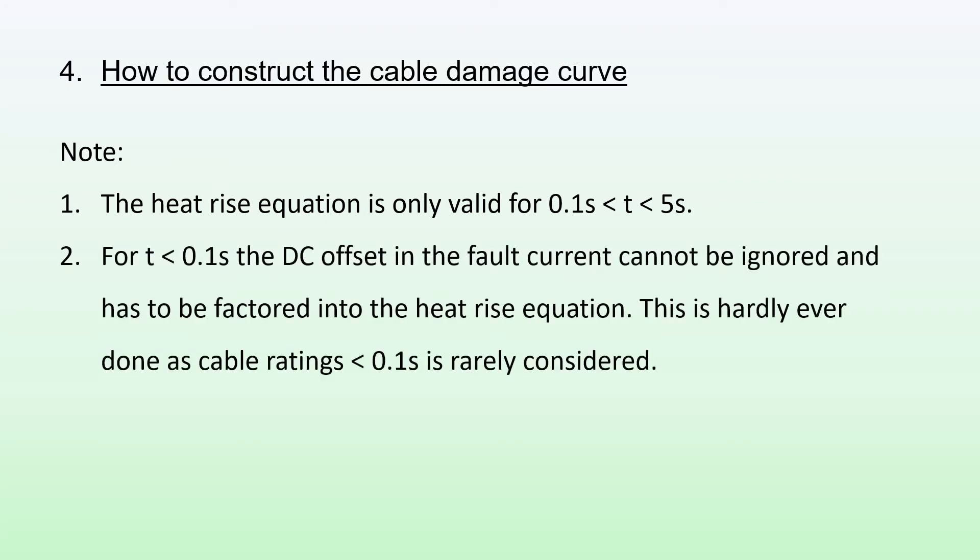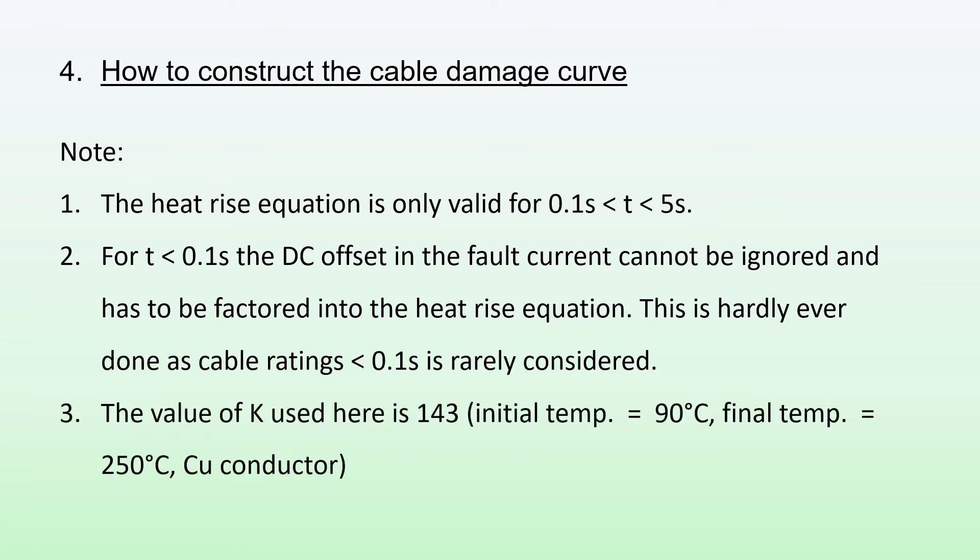Please note the following: this heat rise equation is only valid for the time period from 0.1 second to 5 seconds. For times less than 0.1 second, the DC offset in the fault current cannot be ignored and has to be factored into the heat rise equation, however this is hardly ever done as cable ratings less than 0.1 second is rarely considered. The value of K used here is 143, based on initial temperature of 90 degrees, a final temperature of 250 degrees, and a copper conductor.